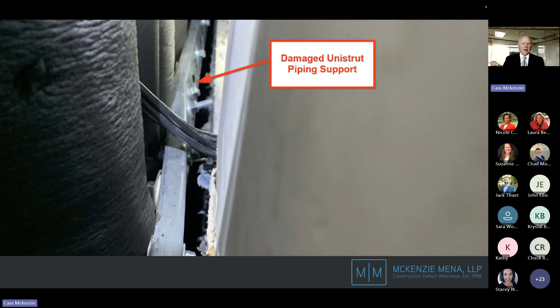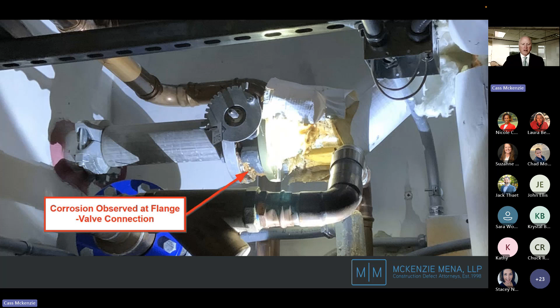Other issues with piping are flanges. Are they properly sealed? Are they letting water escape from the pipe itself? This flange was not properly installed or sealed, so we had water escaping from it, and now it's starting to corrode the flange itself, which is eventually going to make it fail.